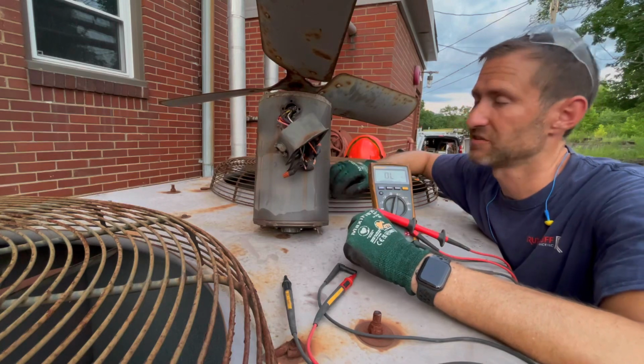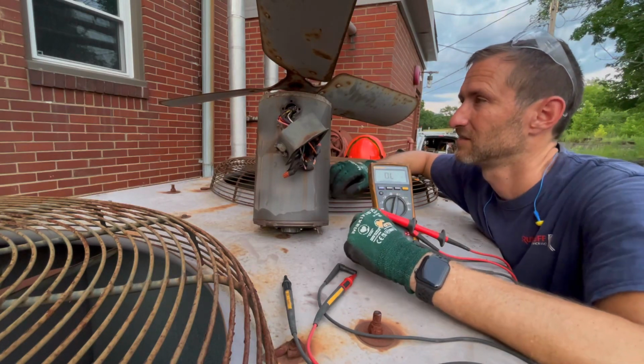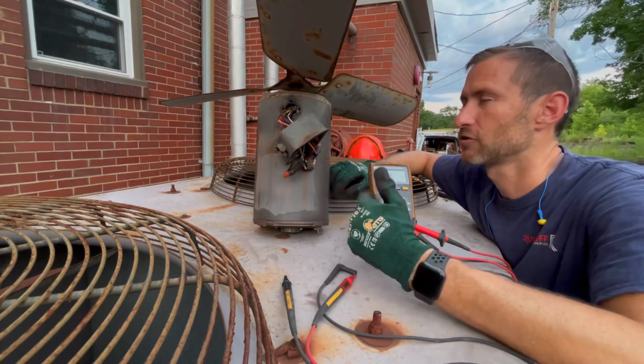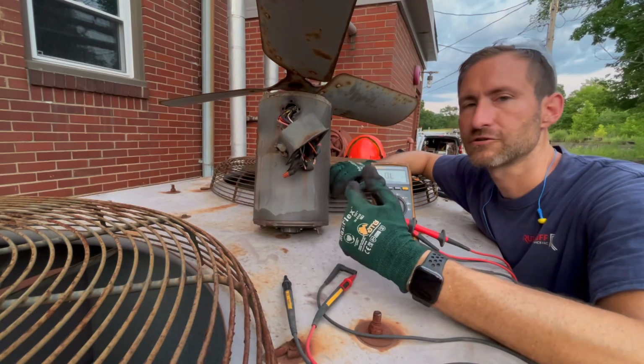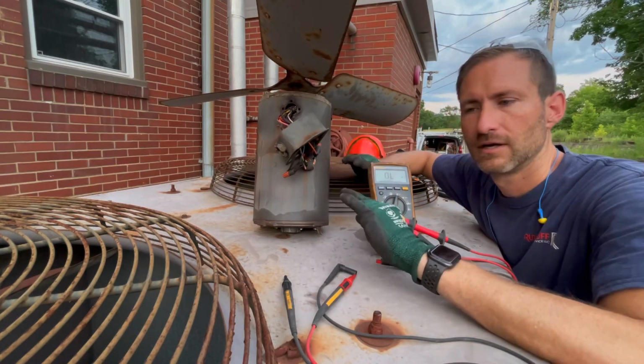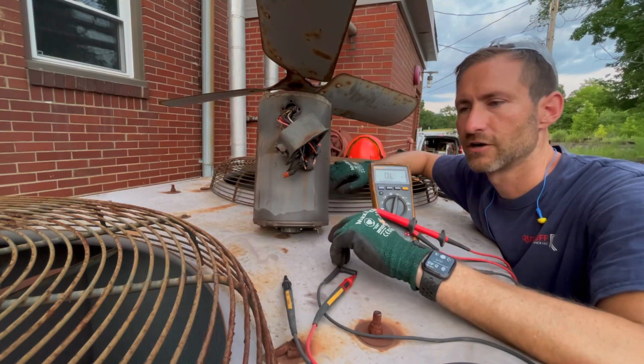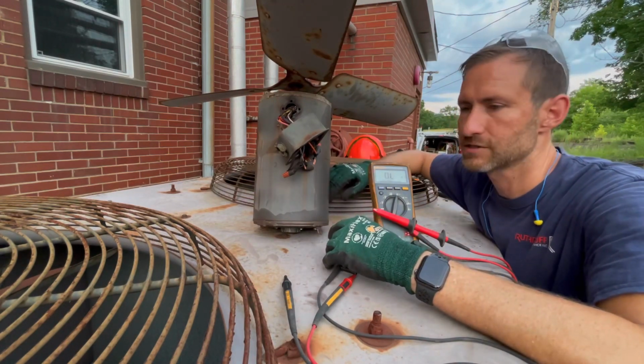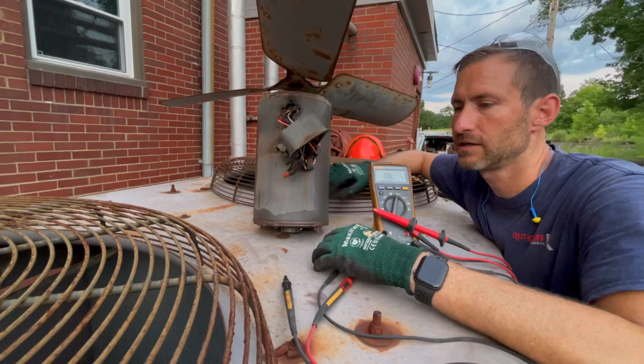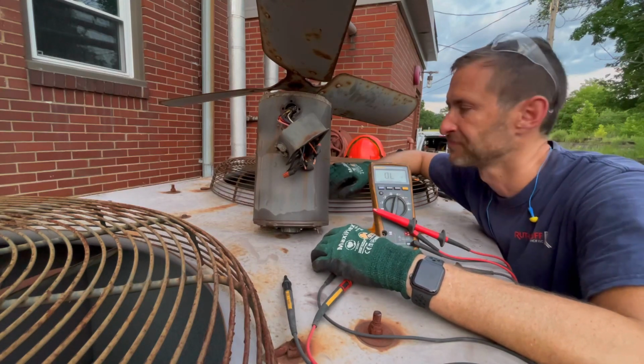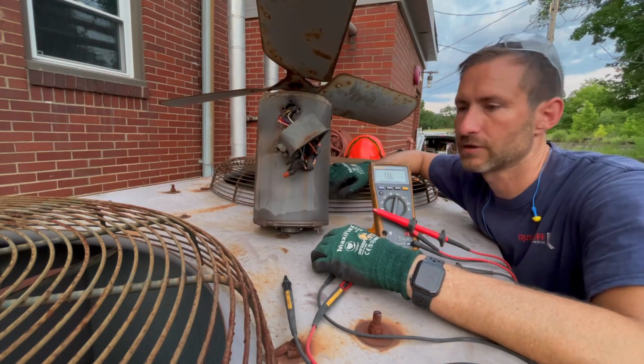Also, maintenance-wise on this motor, you can't do anything. I mean, you can check connections, amp draw, rotation. You cannot grease the bearings, you cannot oil them - they are pre-sealed from the factory. That's it. So they run whatever this chiller, who knows, is - 15, 20 years, maybe older. Might be original motor, I don't know.